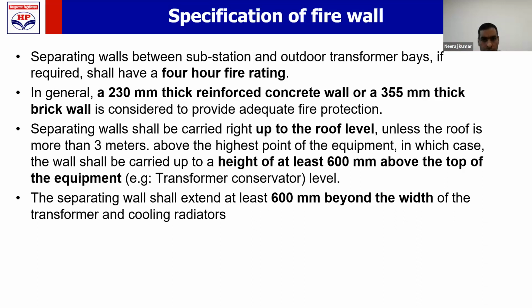Now how can we construct that kind of wall? 230 mm thick reinforced concrete wall. 230 mm की reinforced concrete. नहीं तो 355 mm thick brick wall. So if you are using brick wall, the thickness of the wall should be 355 mm or more. If you are using reinforced concrete, thickness will be 230 mm or more. Such a wall will be considered a 4-hour fire rating wall. Such a wall should be provided around the transformer if you are not able to maintain the clear separating distance.